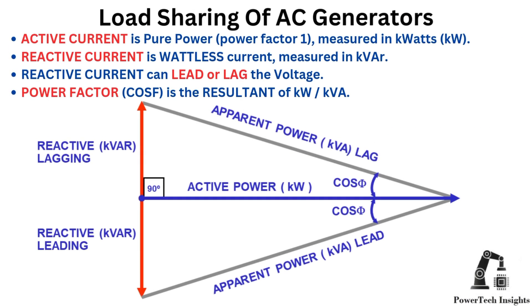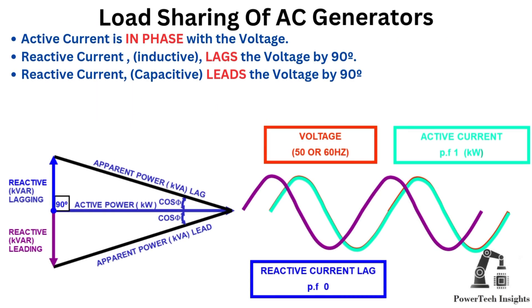Load sharing of AC generators. Active current is pure power, power factor 1, measured in kilowatts (kW). Reactive current is wattless current, measured in kVAR. Reactive current can lead or lag the voltage. Power factor cos phi is the resultant of kW/kVA. Active current is in phase with the voltage. Reactive current (inductive) lags the voltage by 90 degrees. Reactive current (capacitive) leads the voltage by 90 degrees.